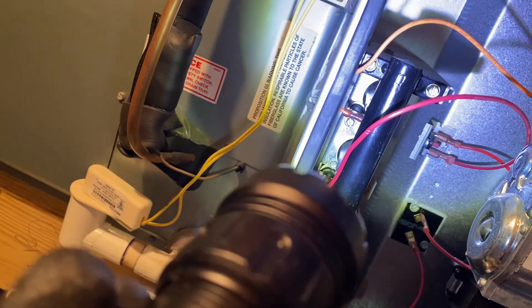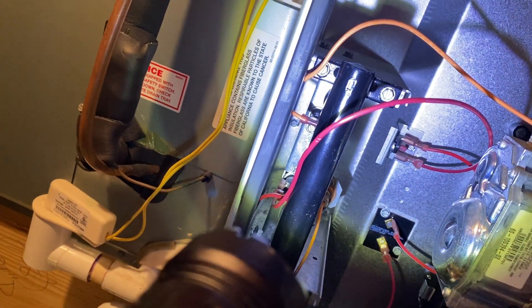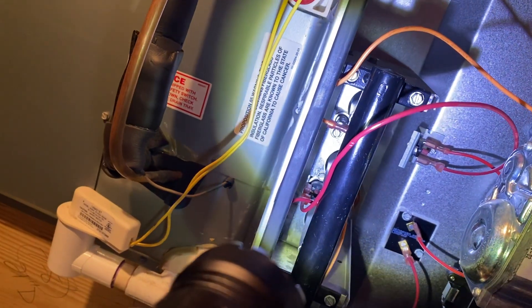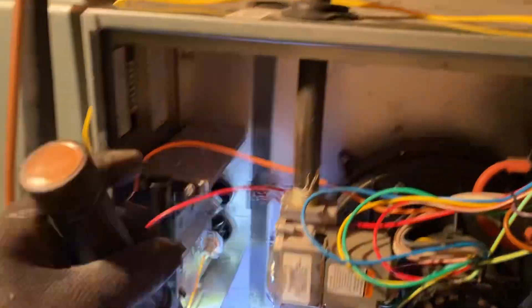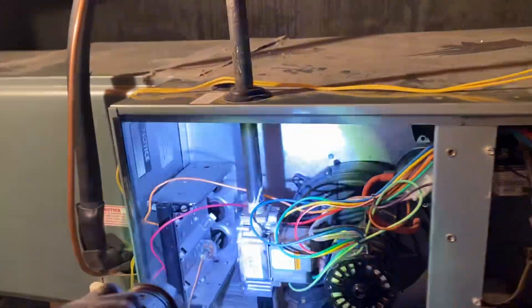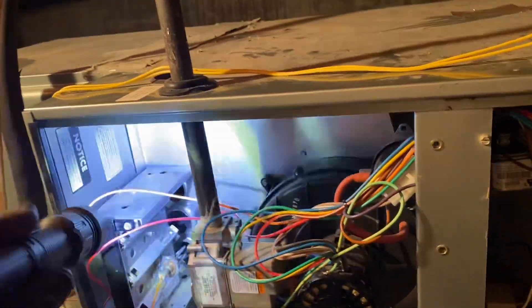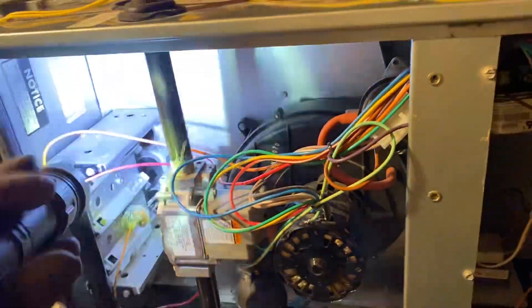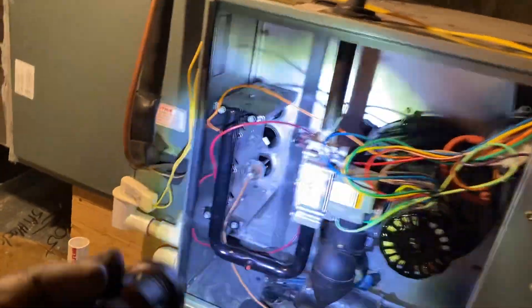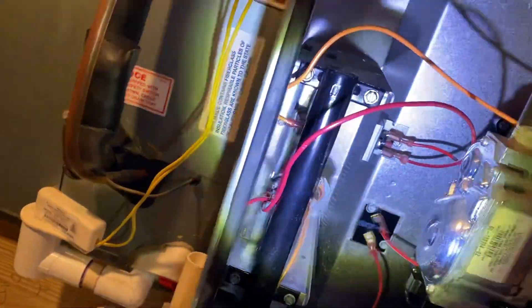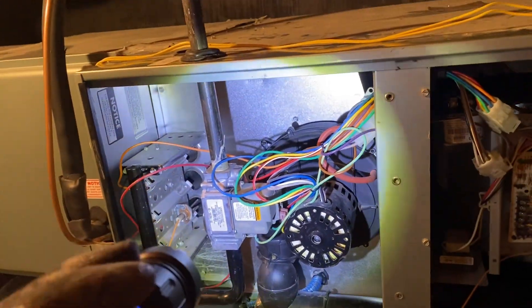I've got lots of videos on those. Rheem does not make them easy to get into. You got to take this out. Sometimes if your hands are too big, you even got to take the burner completely out of there to get to it. That orange wire is a flame sensor.